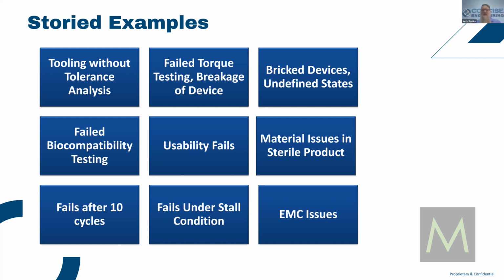We talked about failed biocompatibility testing. I've seen this happen probably 10 different ways, but a couple easy ones are: you change the color of your product and they put a dye in it that was weird. You sent them the right parts and they decided not to do what you discussed, which I mentioned before, Mark, which is just test the outside surface, but they threw the entire thing into a grinder, which had electronics in it. You can be guaranteed to fail. And there are a lot of issues in biocompatibility from a bioburden perspective or an unclean environment prior to shipment. You get mold growth or some other thing on the back end where all the materials are fine, but you still don't pass the test.